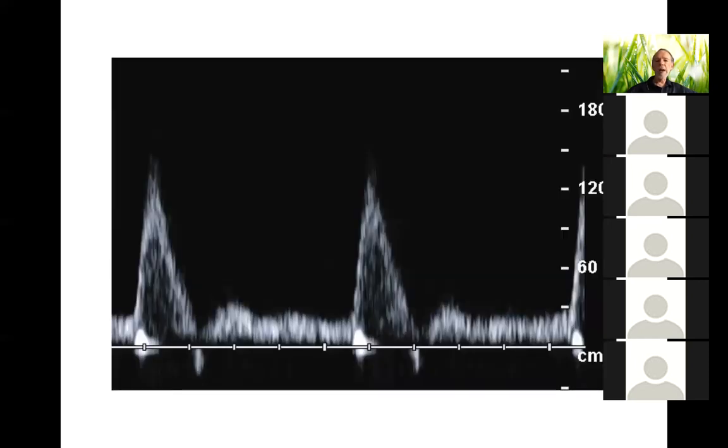You can shift it down, as has been done here, and then you can display a larger range of Doppler shifts above the line, and you've paid a price in that you can only show a much smaller range of Doppler shifts below the baseline. And so moving the baseline is in fact part of standard practice, not so much in echocardiography perhaps, but certainly in other areas, in order to make best use of the Doppler display.